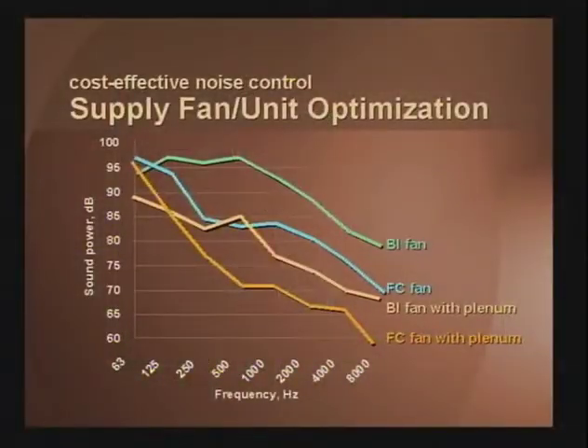This slide right here shows you the difference between two fan types. I ran this at 8,500 CFM, 3.5 inches static pressure. Very typical. It's the fan with a single discharge plenum on the end of it. Notice the difference in the two characteristic curves, the FC fan and the BI fan by themselves. The FC is generally quieter except in the first octave band. If you add a discharge plenum to both of them, both sound levels drop significantly. But the BI fan responds in lower frequencies to the plenum better than the FC fan. And you can see that in this case, the discharge plenum offered the BI fan about a 5 dB reduction at 63 Hz and about 10 dB at 125 Hz. That's very significant and can be a key part of source optimization.